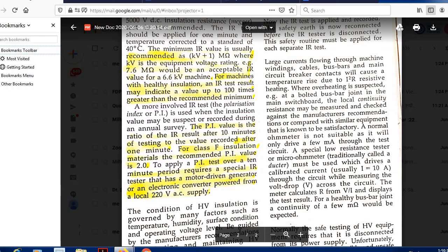So suppose I have to do some check on the high voltage system. Suppose I see that the bus bar is there in the main switchboard, and then the bus bar is clamped, and suppose it is loose and there is arcing which is taking place, or there is a hot spot developing somewhere.